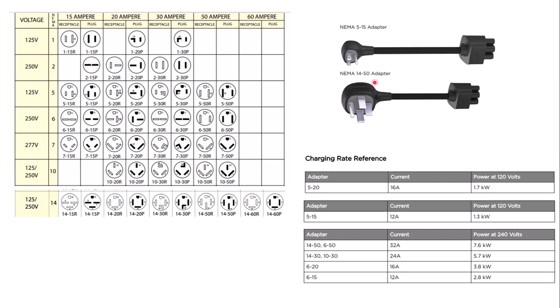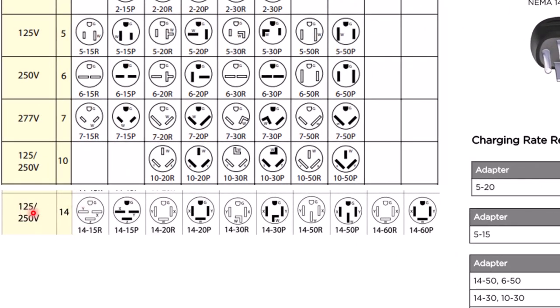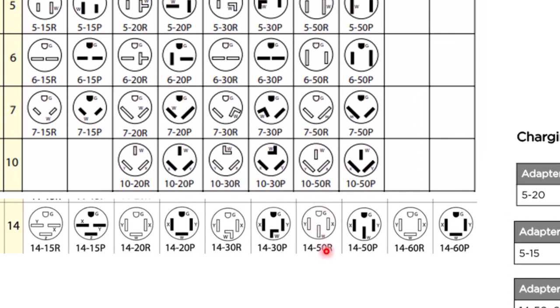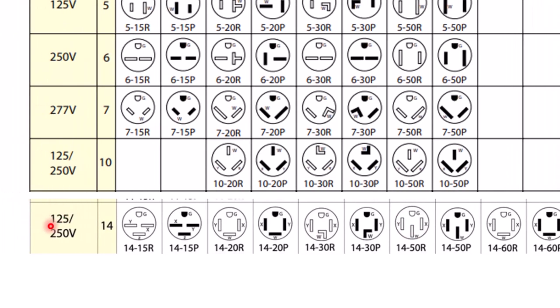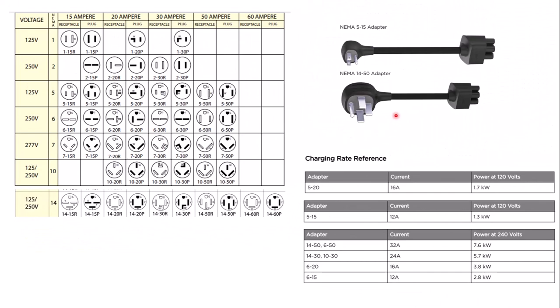Now you can have a NEMA 14-50 adapter, and these are typical for electric clothes dryers. So if you look down here, this is the NEMA 14, and they're rated for 125/250 volts. Okay, so there's two ratings here because if you look at the shape of it, let's look at the NEMA 50, for example, this one here. You can see that there's a ground, which is here. And then you have a W, which stands for white. So this is probably the neutral. I'm not 100% sure, but one of these three are the neutral, and the other two are the 120 volt hot legs. So one hot leg and the neutral would make the 125 volts. And then the two hot legs would make the 250 volt out of this rating here. So that's why you see two of these ratings. And then you have a G, which is the ground. So that's what these NEMA ratings would look like.